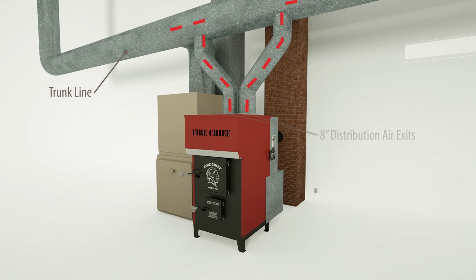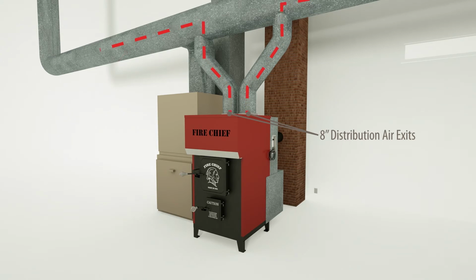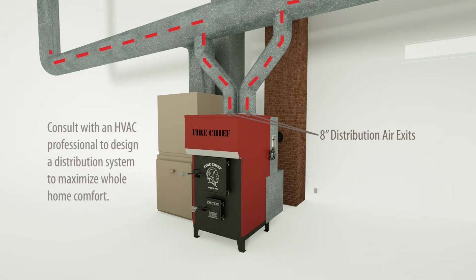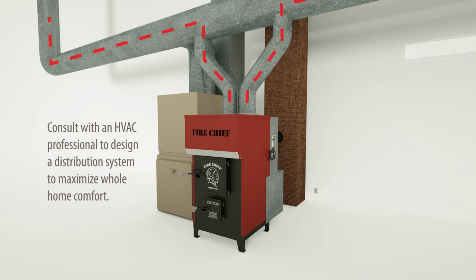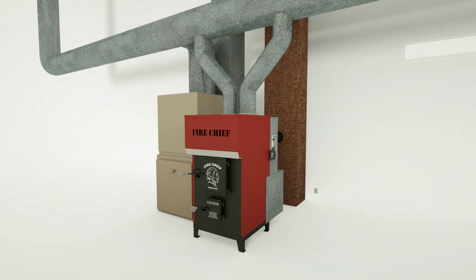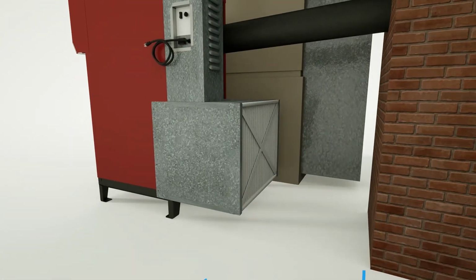If you are installing this furnace as a standalone heating system, you can connect the 2 8-inch distribution air exits directly to approved venting materials. As we mentioned, you may want to consult with an HVAC professional to design a distribution system to maximize whole home comfort. The return air enters through the filter box located on the back of the unit. While providing warm air to your home is important, equally important is planning for adequate return air to ensure that the furnace will function properly.